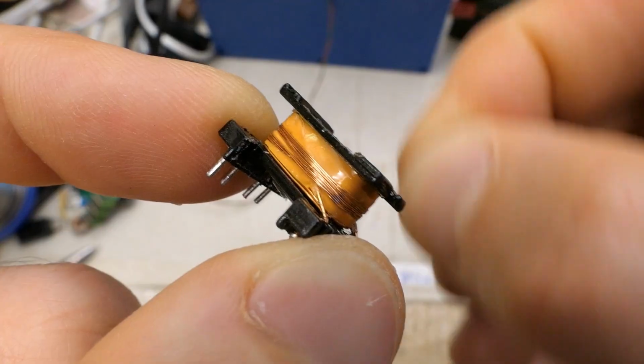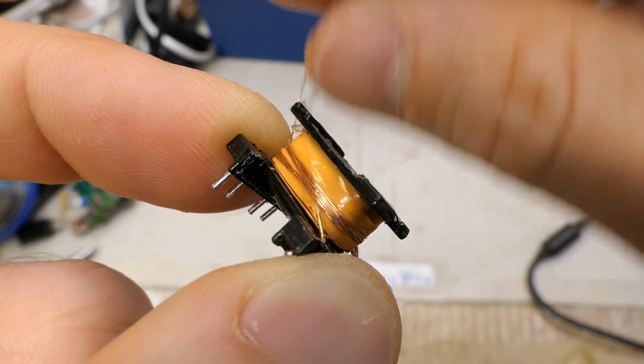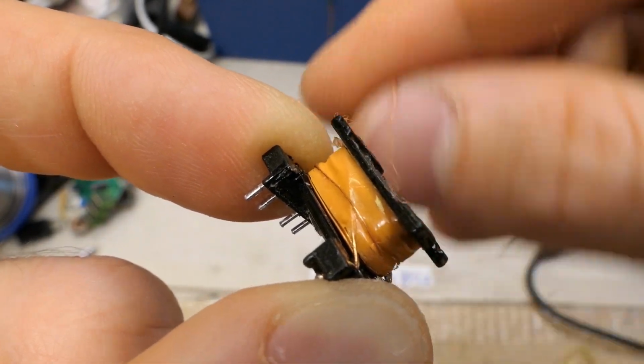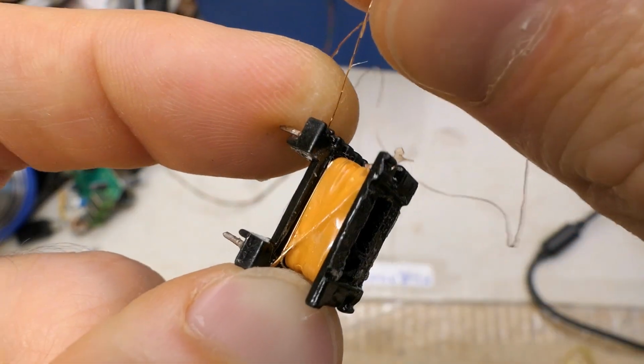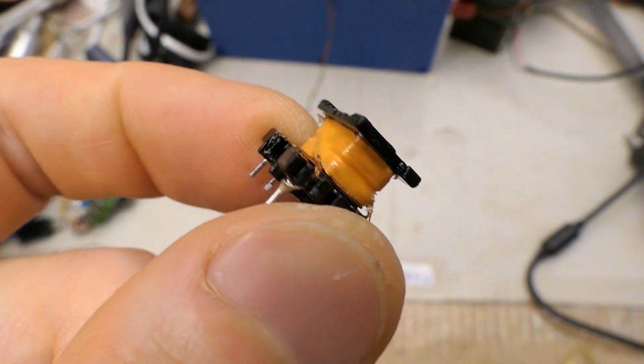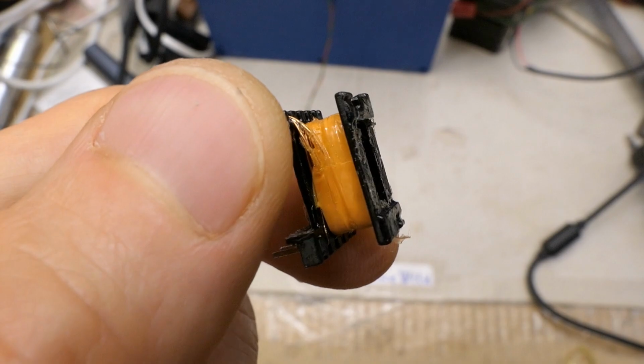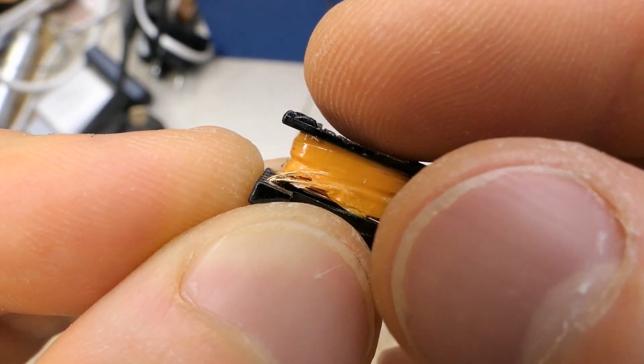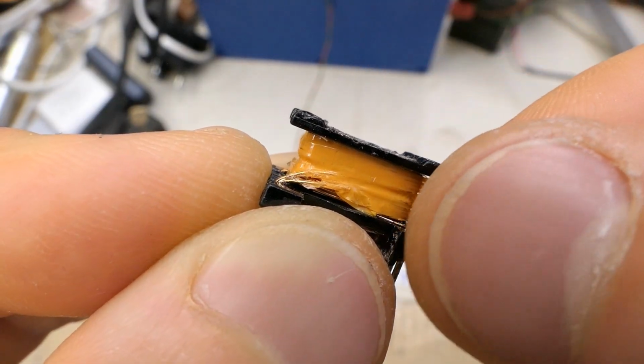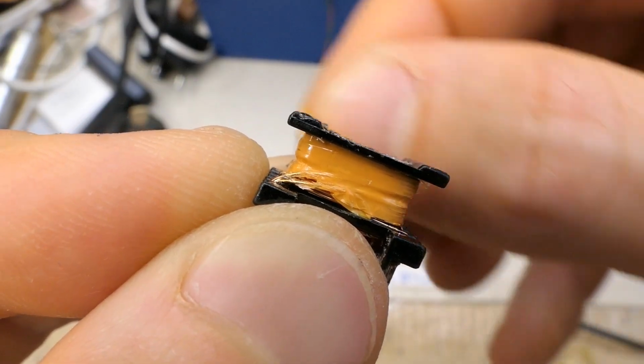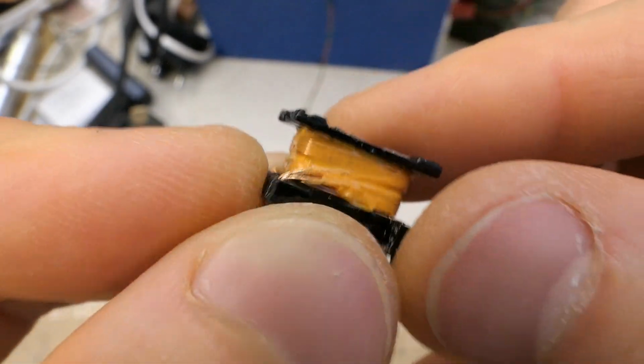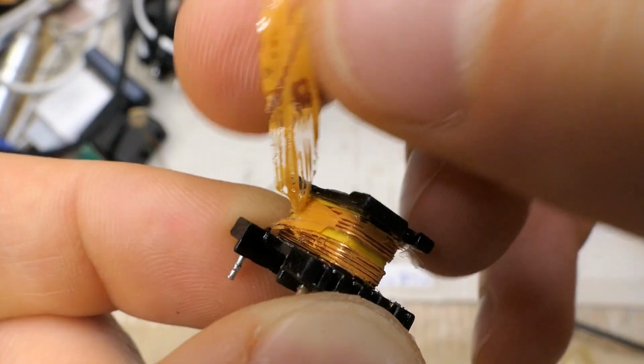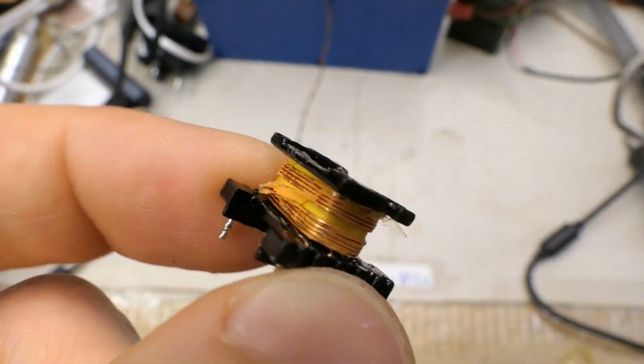Let's remove the auxiliary winding and explore further. Here is the insulation, which is melted and has gaps, and it's absolutely not made of a thermally resistant material. It's not even easy to remove — it's sort of melted onto the wiring.